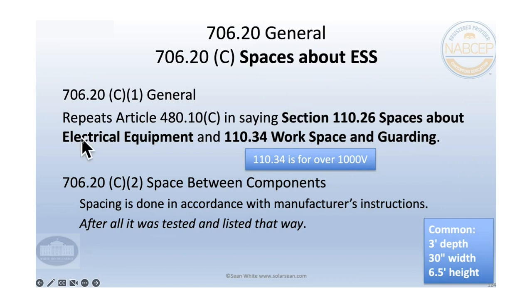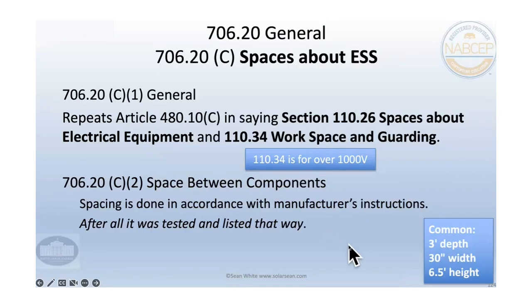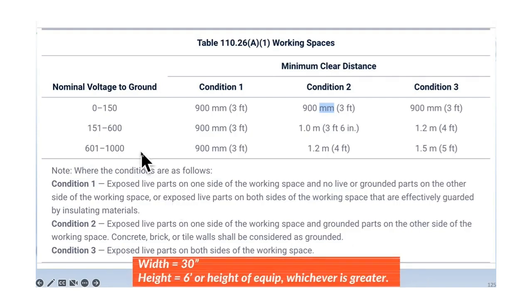So here's a little bit about spaces between components. And this is just general, same for other things too. If we go to 110.26, we usually, like your typical residential system, 3-foot depth, 30-inch width, or the width of the equipment, of course, and 6.5-foot height. And if somebody's over 6.5 feet tall, then they are already retired and make a good salary playing baseball and basketball. They're not working with us anyway. So here's just some of those working space requirements. You're probably already familiar with all that with PV.